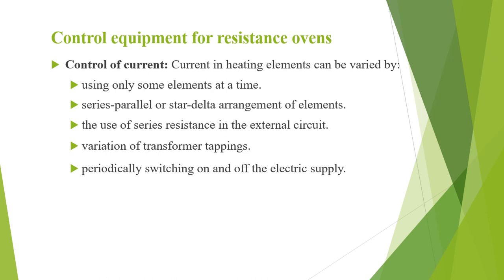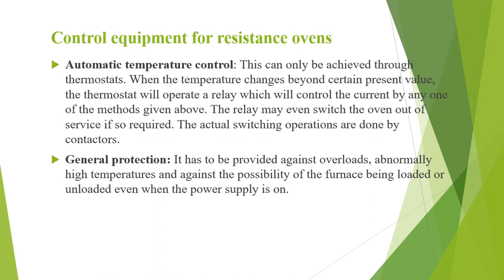Other methods of current control include: use of series resistance in the external circuit — this is wasteful in power and therefore uneconomical, but sometimes used for small units due to low cost and ease of control; variation of transformer tappings, only applicable where a transformer is used for stepping down the voltage; periodically switching on and off the electric supply — the final temperature is the ratio of on-time to the sum of on and off time; and automatic temperature control through thermostats, where the thermostat operates a relay to control current by any of the above methods.